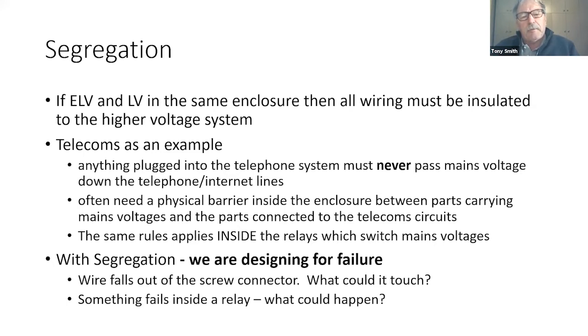So you've then got to think about how you can work around that. The rule is, to give an example, in telecoms you must never pass the mains down the telephone or internet lines. So what you quite often do is need a physical barrier inside the enclosure to separate, to effectively create two enclosures, to get around this problem of everything needing to be insulated to the highest voltage. The same rule applies inside relays and any other device you've got - things like optocouplers do that, but not every relay would meet that requirement.